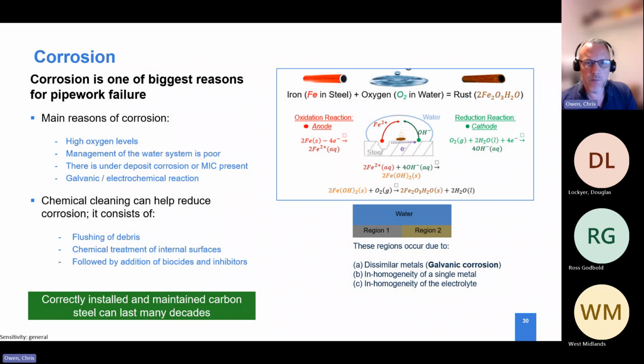Corrosion is pretty well understood, and it's one of the biggest reasons for pipework failure based on the data we've got. We do know the reasons behind corrosion in open and closed systems. An open system is going to have more oxygen in, however closed systems can also have the same amount of oxygen, particularly if they're leaking or somebody hasn't made sure that system is leak tight. So understanding what we call the electrochemical reaction, where oxygen plays a key element.